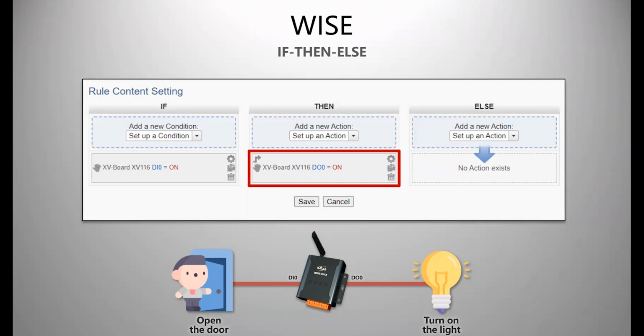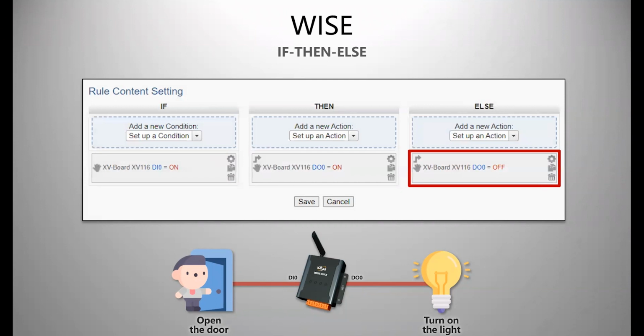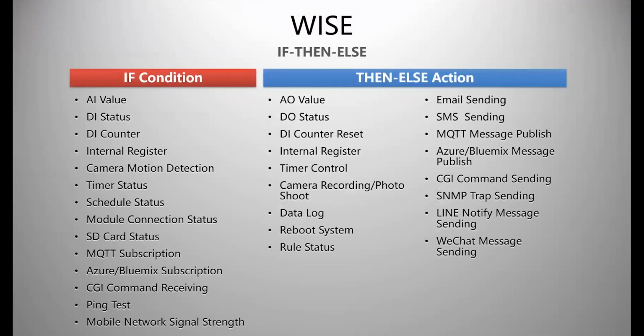And now we are going to do the same thing for else. Here we set up an action and choose DO. However, here we set up the status of DO as off. And now we complete the control logic. When the DI is on, the DO will be on. Otherwise, the DO will be off. So when the door is open, the light will be turned on. So as you can see, we can complete a control logic without any programming and development environment. And here are all the parameters we can use for if condition and then else action.